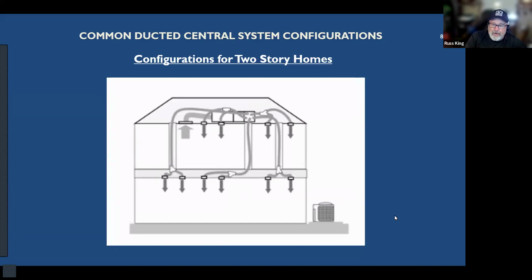Okay. Very, very common. If you have a two-story house with only one system in it, the way they typically do it, at least for tract homes, production homes, is they'll put a horizontal unit in the attic, and the upstairs will be served by ceiling registers. And then the downstairs, they have to get ducts from the attic all the way down to the first floor. And they'll do it through these cavities called chases. That's a chase. Okay. C-H-A-S-E. And they'll just run the ducts down through there, and then the ducts will get to the first floor. But now, how do they get from that point over to the rooms that they need to get to? And that is, I ran two mechanical engineering departments, and that was probably 80% of my headaches came from trying to get the ducts from the bottom of this chase over to the room where we wanted that supply register to be.